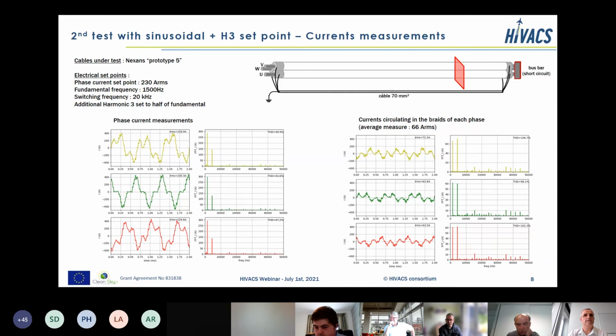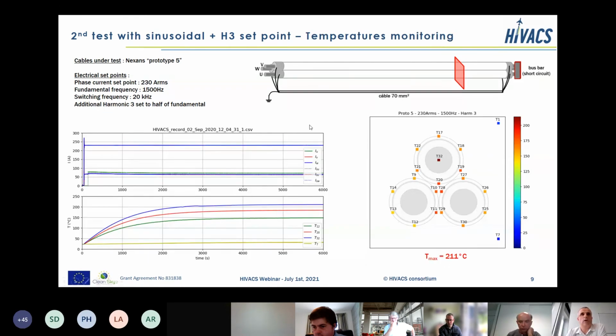What is interesting is that the induced current in the shield is not the same waveform as before. Due to the higher frequency of the harmonics, the induced harmonic 3 is higher than, or quite the same as, the fundamental induced harmonic. So it's quite interesting. It means that depending on the harmonic content in the conductor, we don't get the same induced currents in the braid. In this case, we got more induced current because instead of 50 ampere, we now got 66 ampere. And that's why we have more losses in the braid, and so in the outer cable in this configuration.